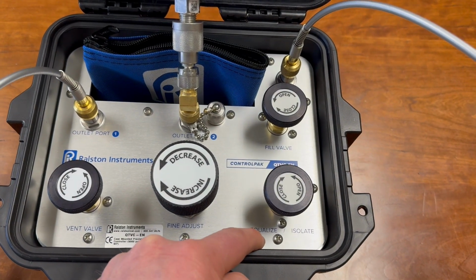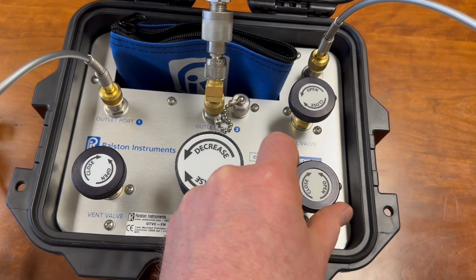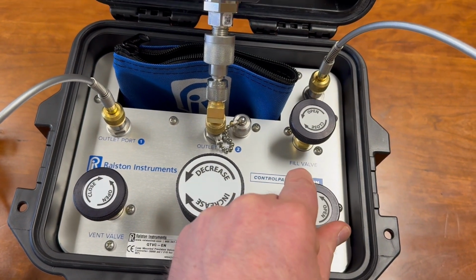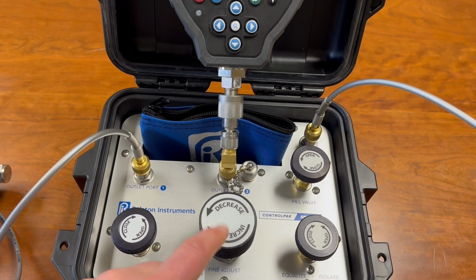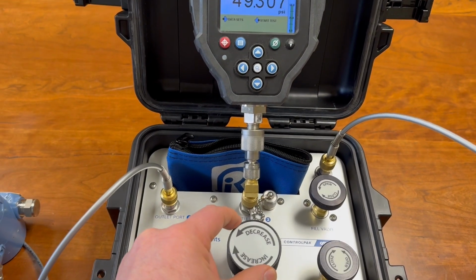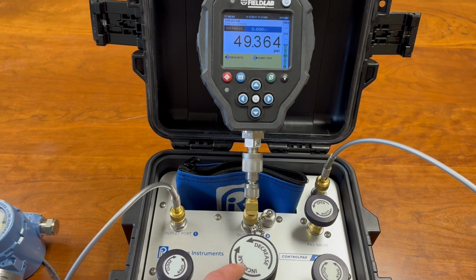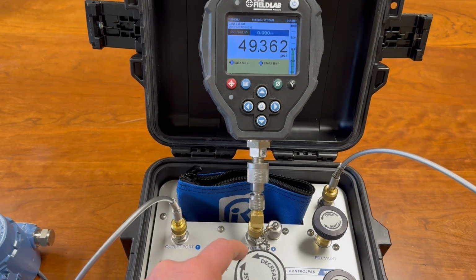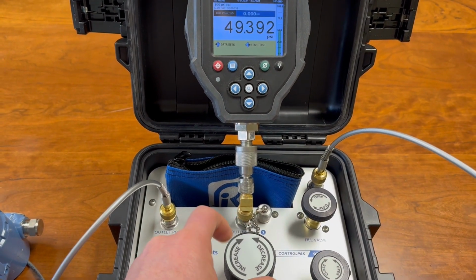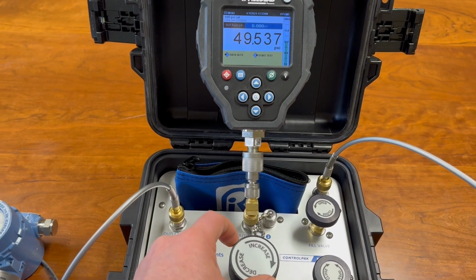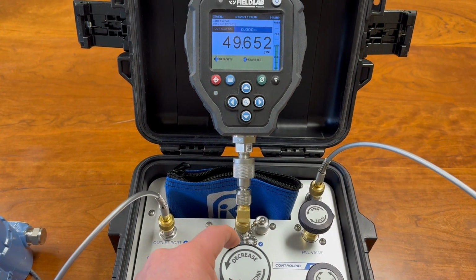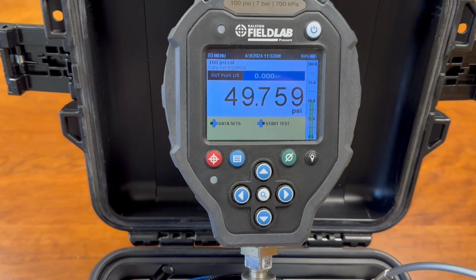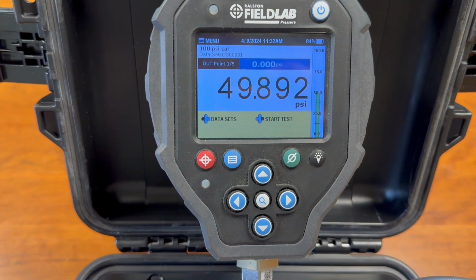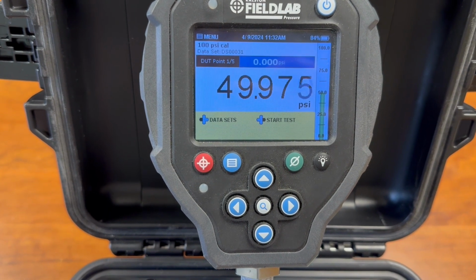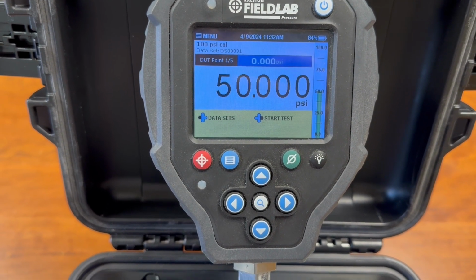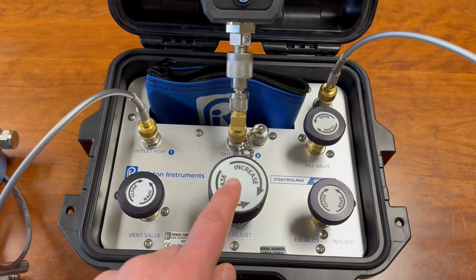We're going to close the equalize isolate valve. When we do that, now the fine adjust piston can have nice fine adjustment of the pressure, whether it's at 2 inches of water column or 3,000 psi. You have very, very fine grain control. So you can see here, bringing up the pressure until we're at exactly 50 psi. Okay, so that was our first test point.